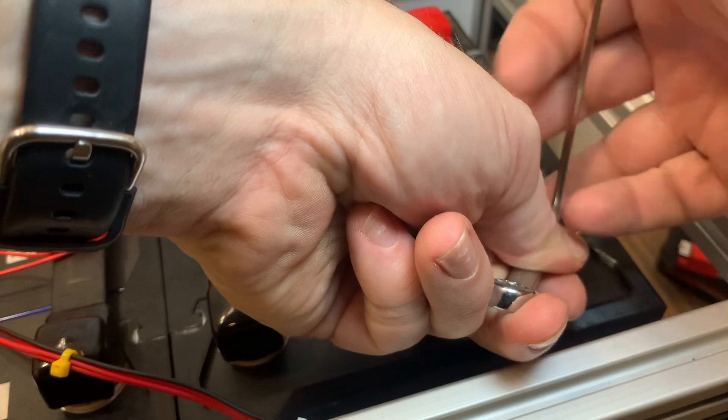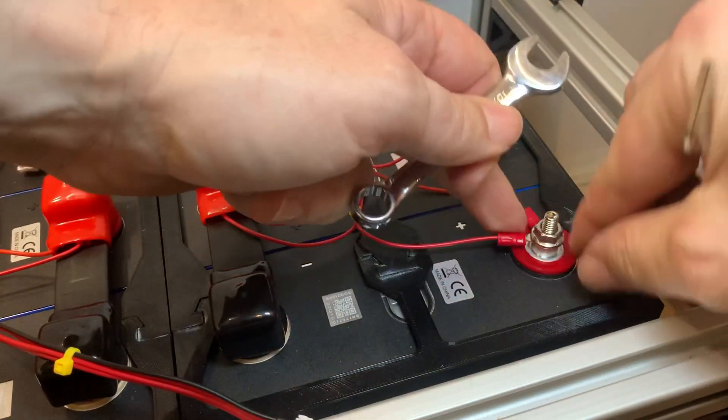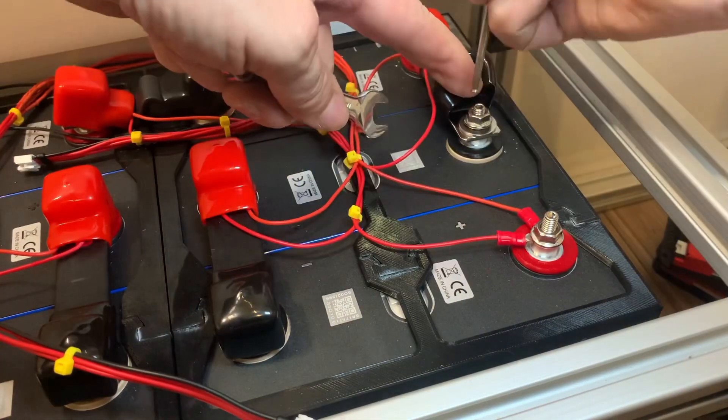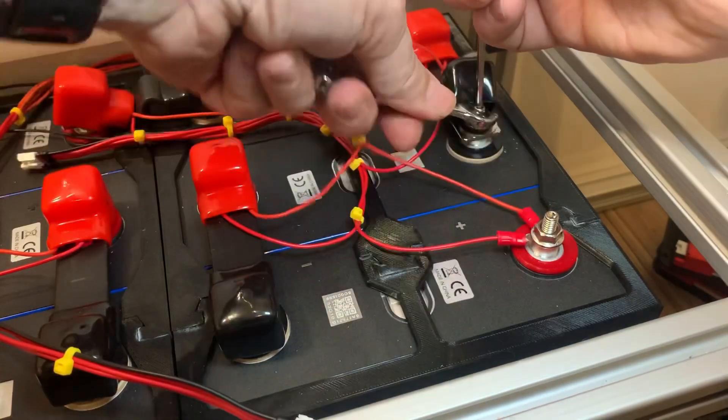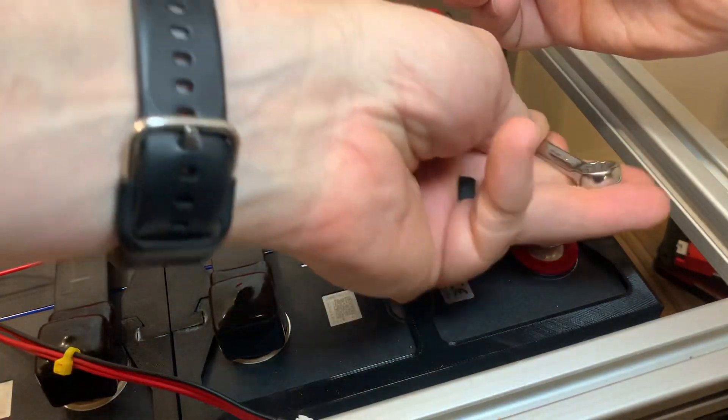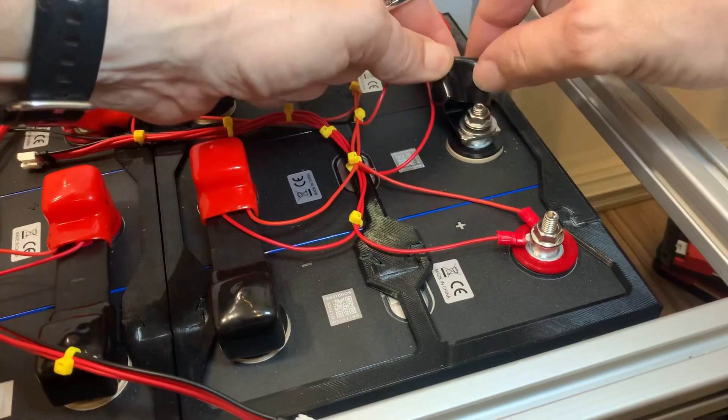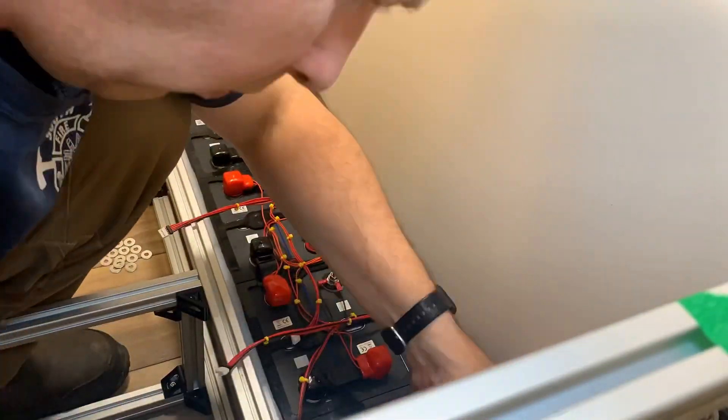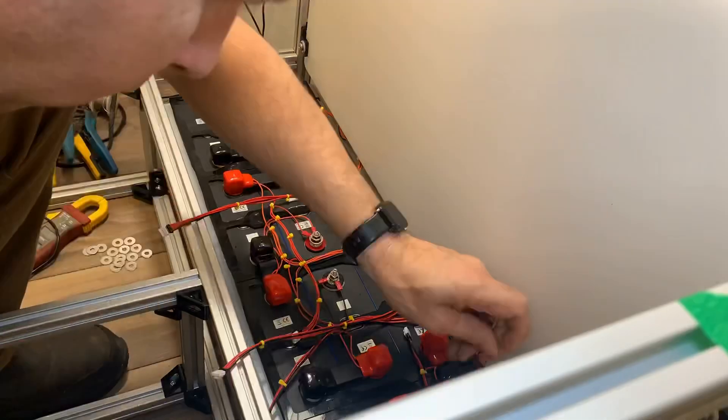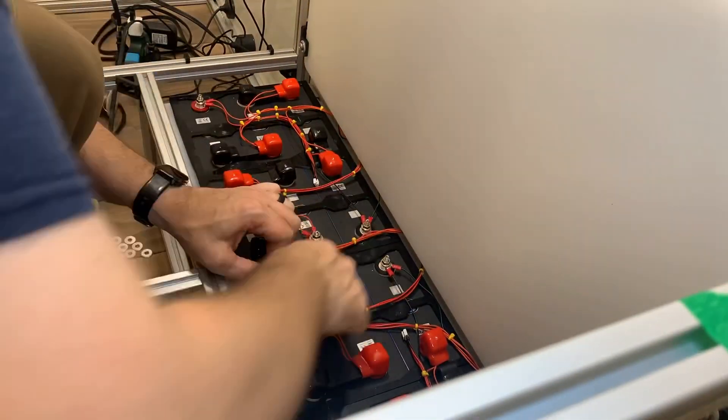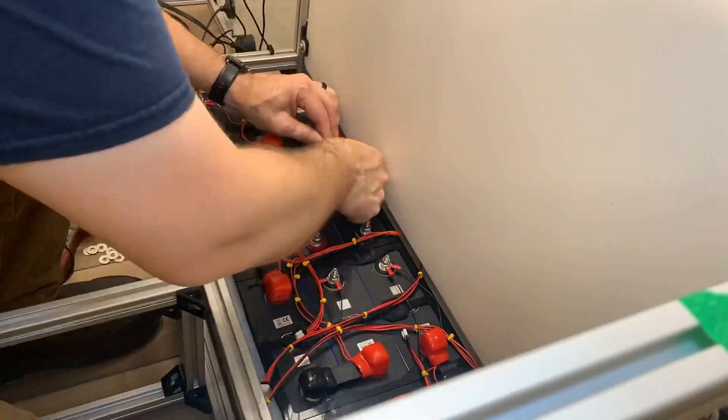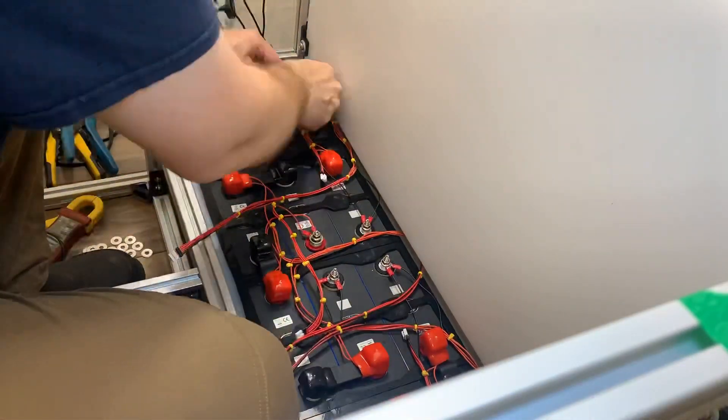And now that I'm working on a live battery system, I'll address a concern that someone raised in the comments a few videos ago. See if you can see the difference. When tightening the nuts down, I'm holding the stud still using the allen key to stop me from over-torquing the stud and stripping out the top of the cell. You'll also notice I'm using a stubby wrench and cradling it with my hand. This gives me some protection against shorting out to another cell terminal, but ideally I'd be using an insulated wrench handle. I'm tightening down all of the terminals except the three main positives and negatives. Did you catch the difference? I bet a few of you did.